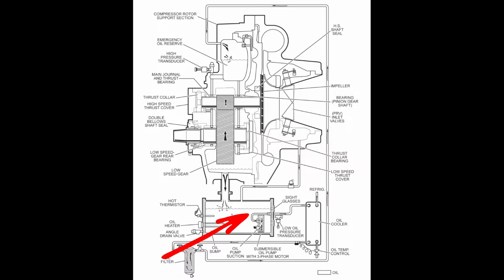And one, just verify, is that even correct? One of the ways you can do that is taking a line temperature leaving the pump. So if we're concerned that maybe that temp sensor is not reading correctly, I can compare that to my leaving sensor coming out of the pump, or the oil discharge line coming out and going into the oil cooler.